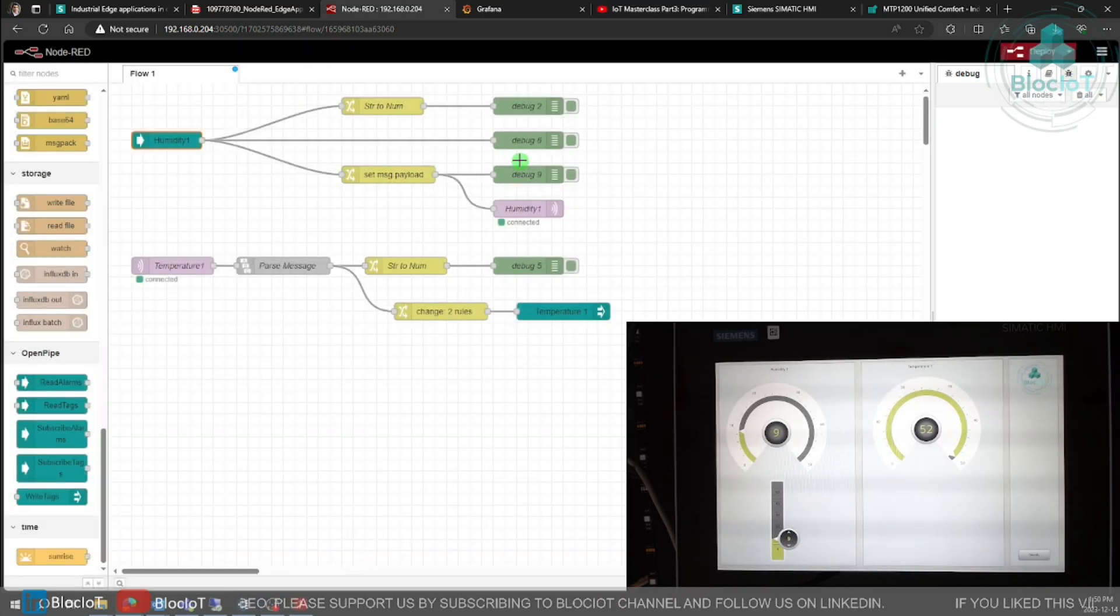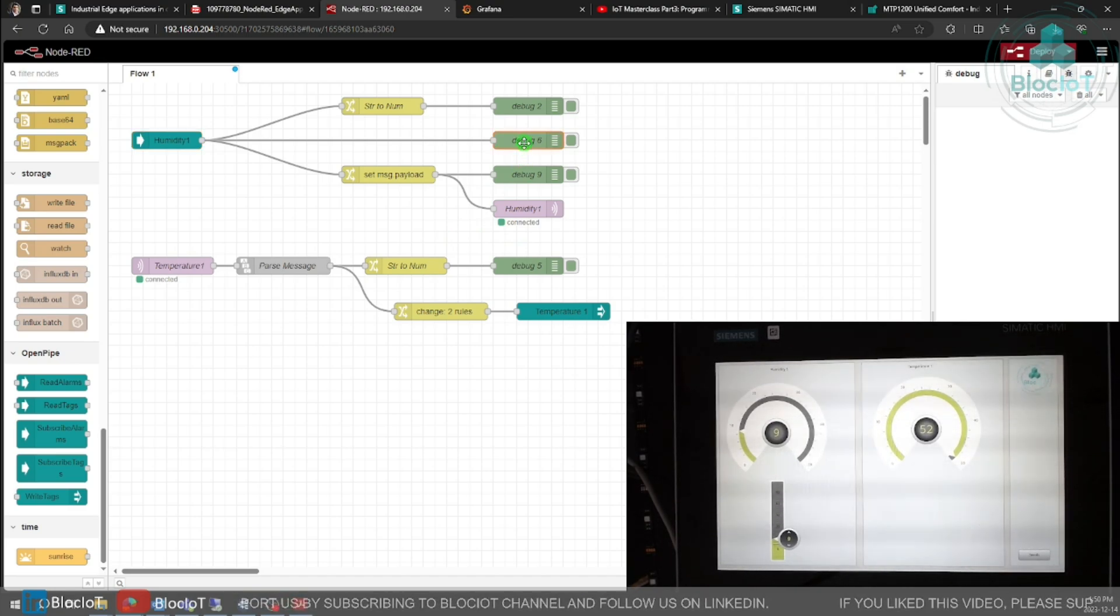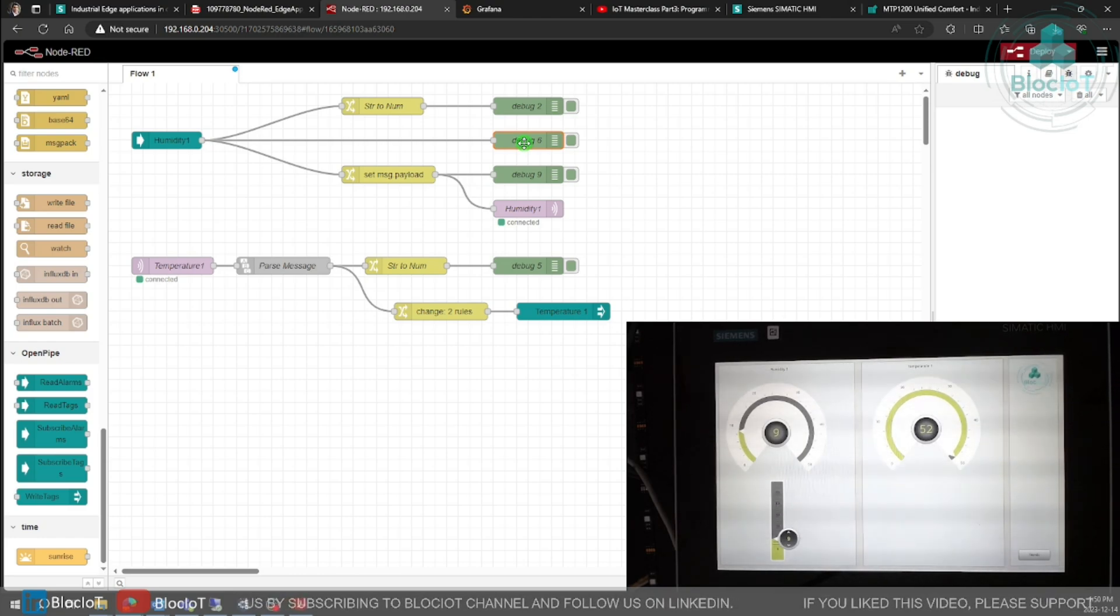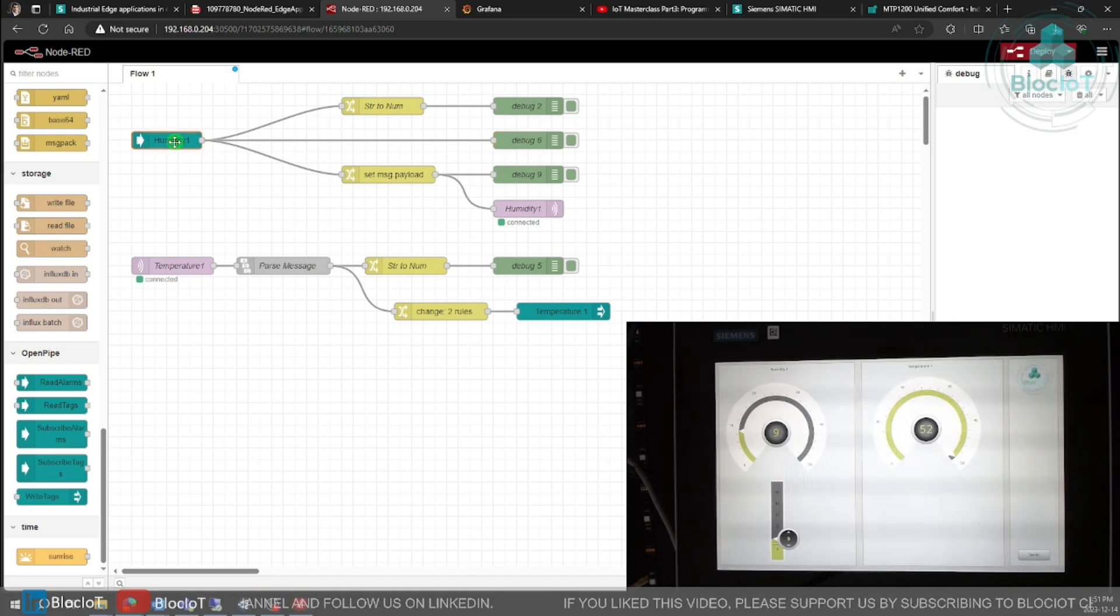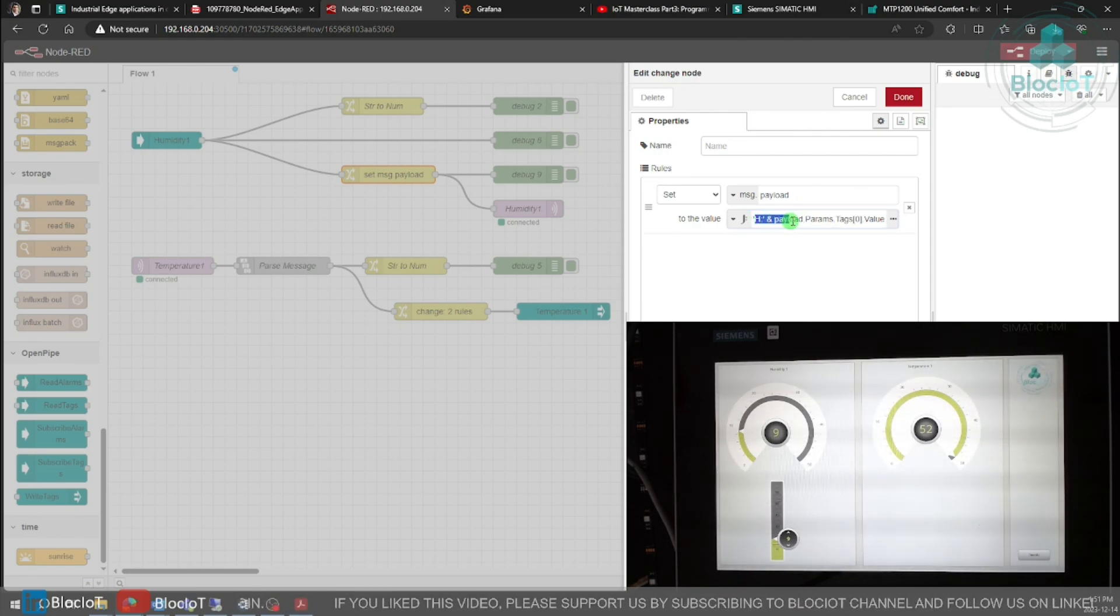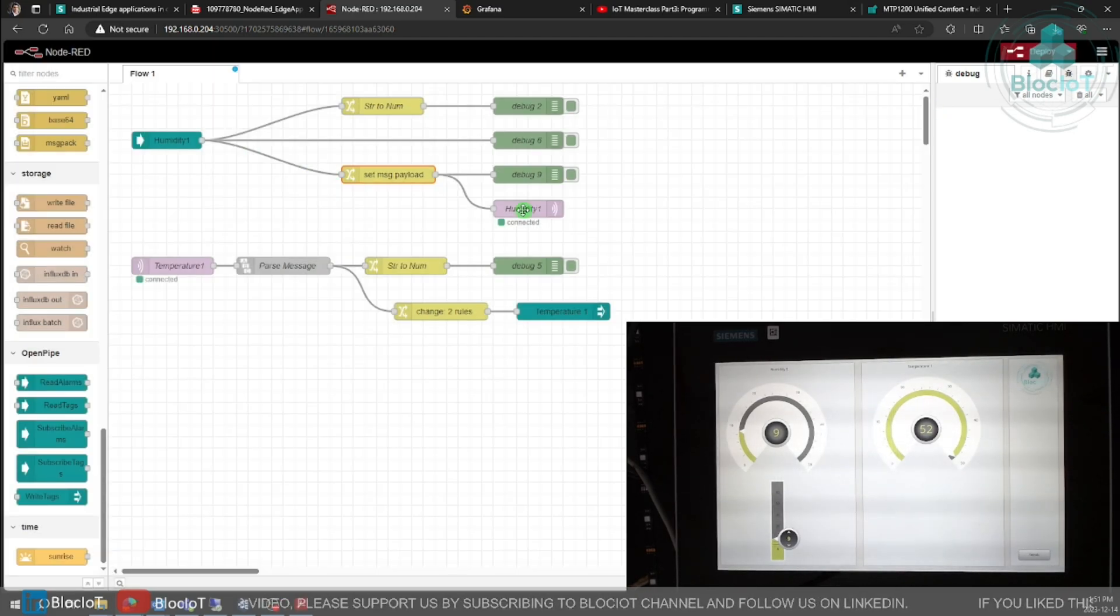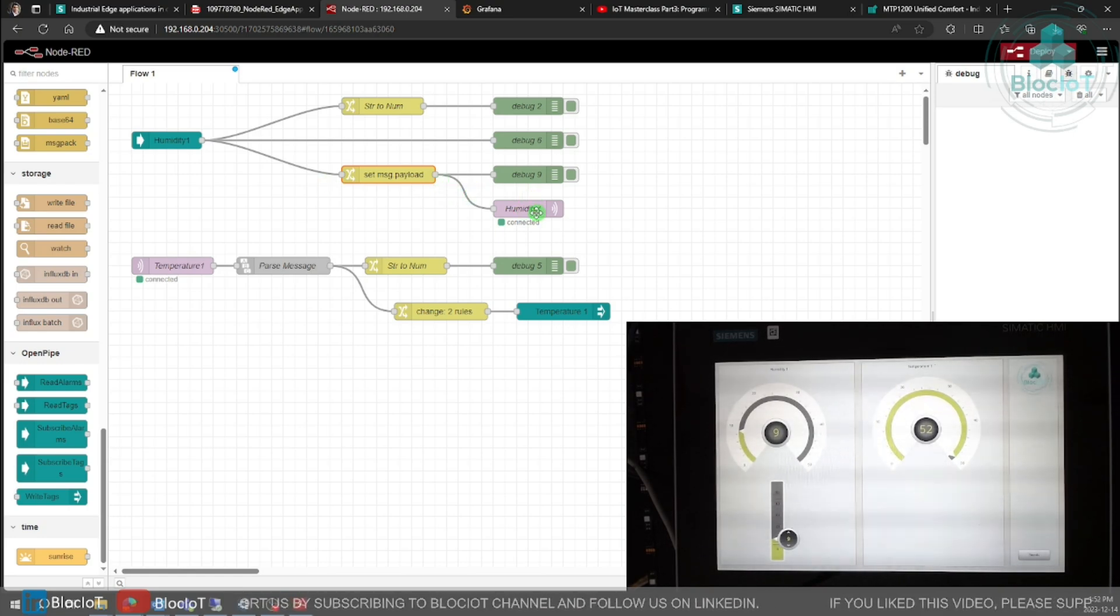You can monitor the raw values that are coming from this node using a debug node, but for sure we need to do some data manipulation on the incoming data to convert the raw data into our desired format which we have defined previously. After reading the HMI tag we convert it to our desired format. I can show you quickly here, I'm just using a change node and I'm just adding this edge semicolon and the value of that tag, and ultimately I'm using an MQTT out node to send my tag value to the MQTT broker.